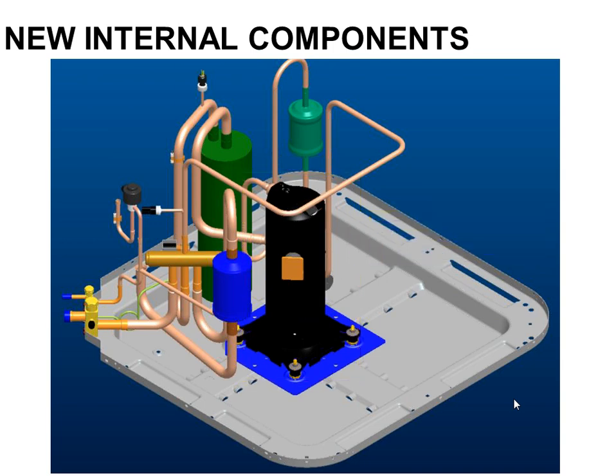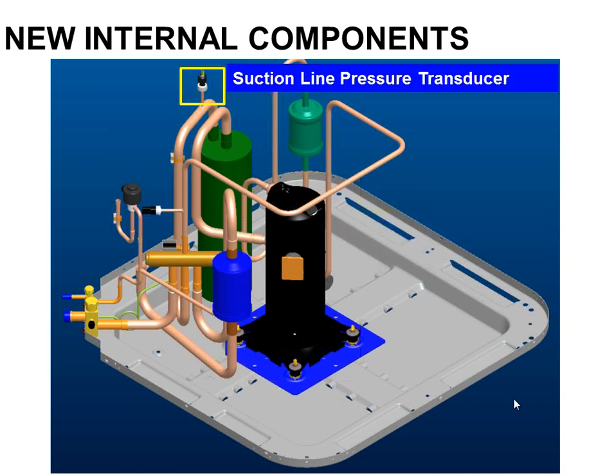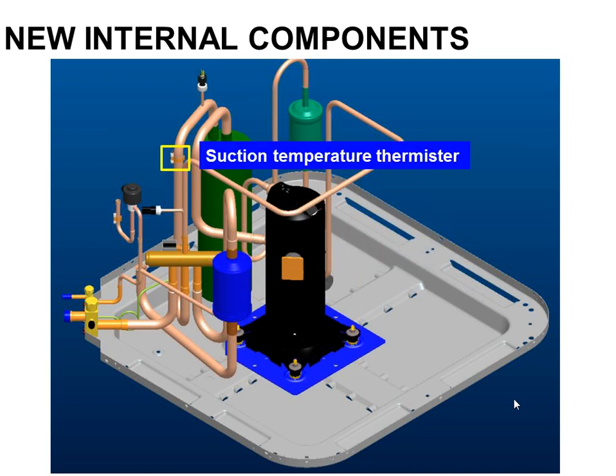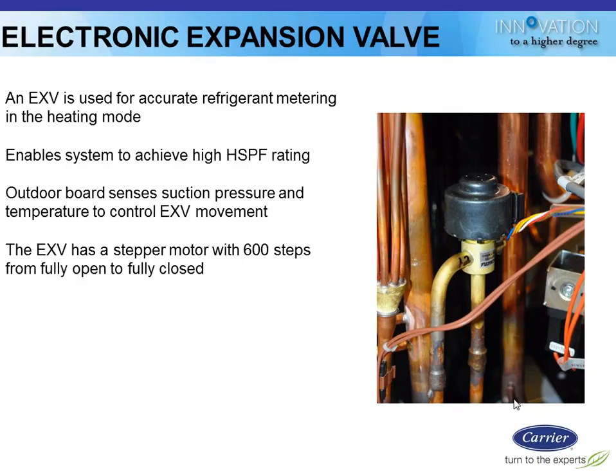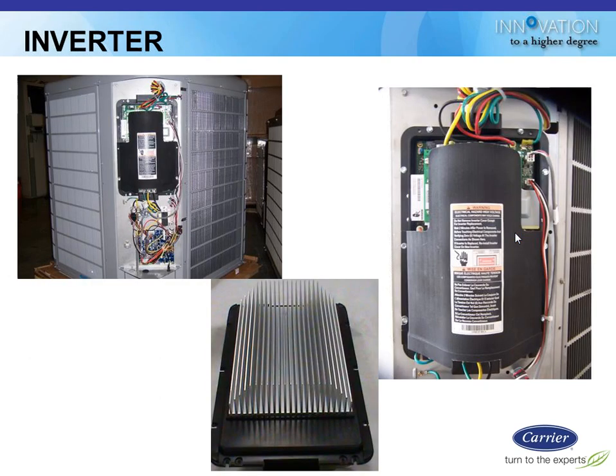Variable DC compressor. There's some extra sensors on here. There's a suction line pressure transducer. There's also a suction temperature thermistor that are feeding back into the controller. There's the expansion valve, 600 steps. He's that little black guy right there. It's like the top of a beer can kind of thing. That's the inverter, the VFD. So you can see electronics on the side of this unit. That's the access section as well.